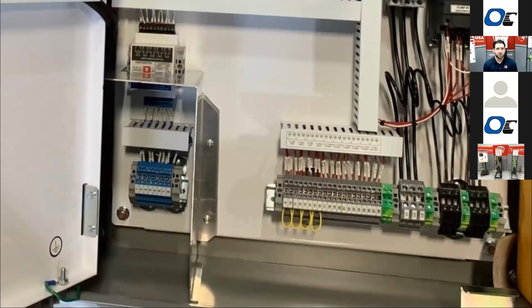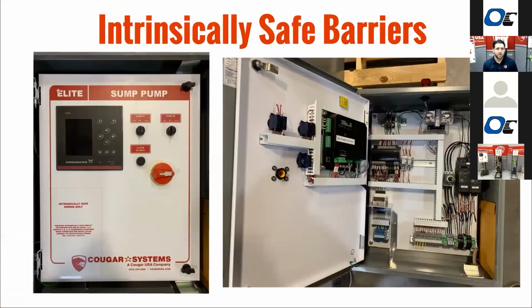And I guess there's a little zoom in there. So there's that electronic barrier, and then the physical barrier here to separate out the two. If we don't have that physical barrier, the enclosure size has to be bigger to meet the UL requirements. And again, this would be used anywhere it's deemed a hazardous location and is required.